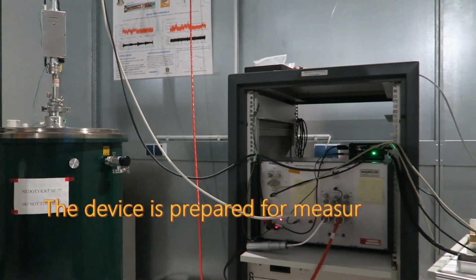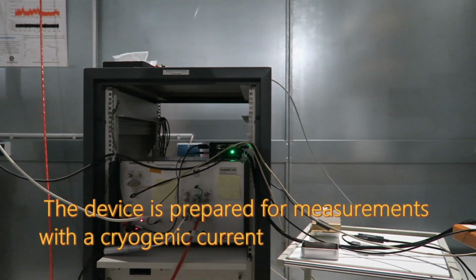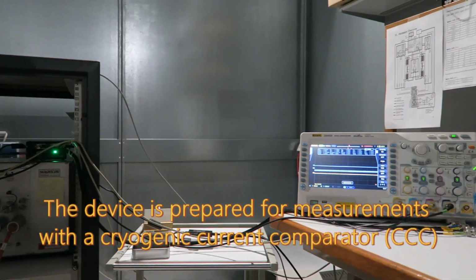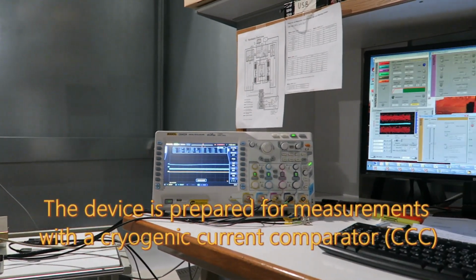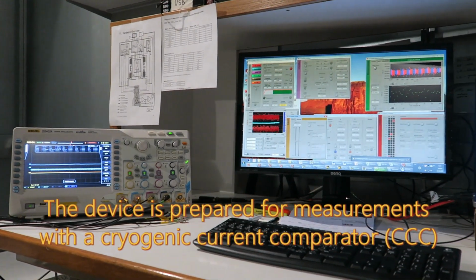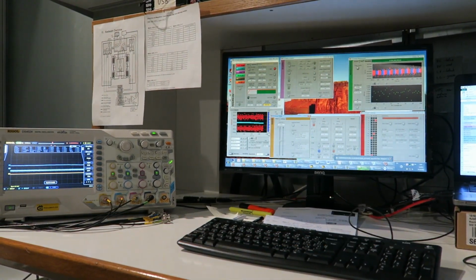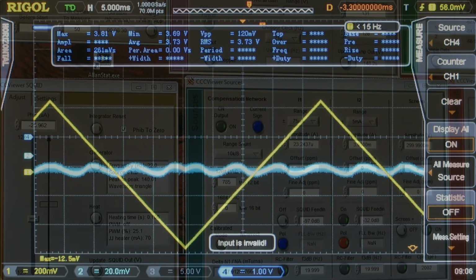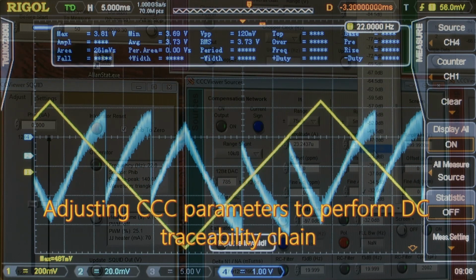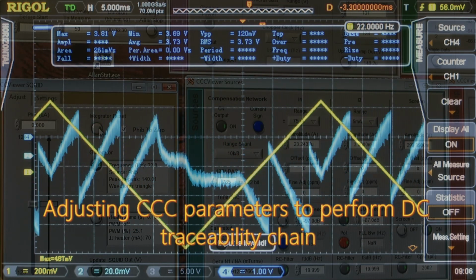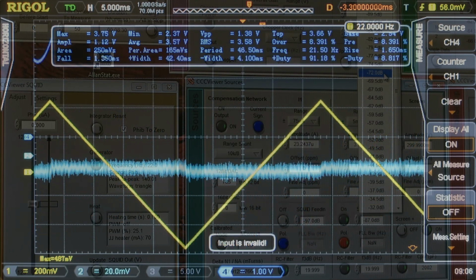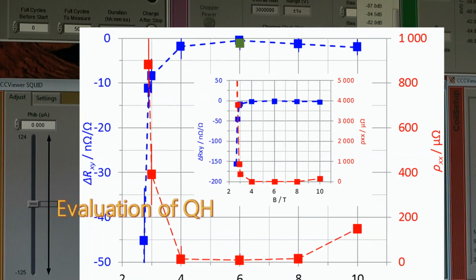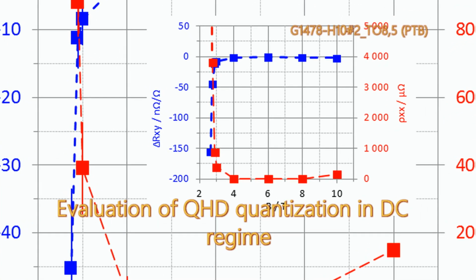When position of the well-quantized plateau is identified, the device is prepared for high-accuracy measurements with cryogenic current comparator. In the next step, operation conditions of the cryogenic comparator are settled and we can start with evaluation of the device quantization in DC regime. For example, the device shown here is well quantized in the field of about 4 Tesla.